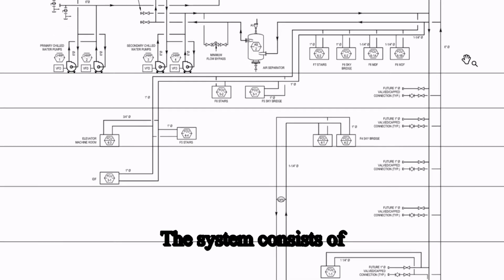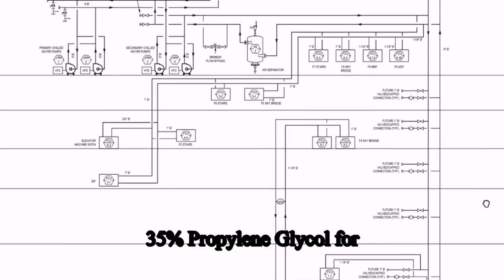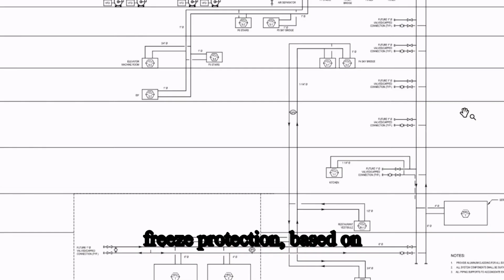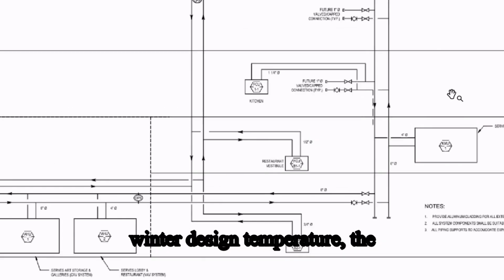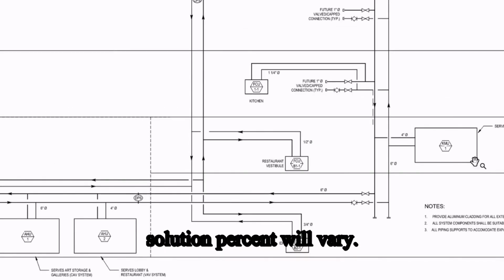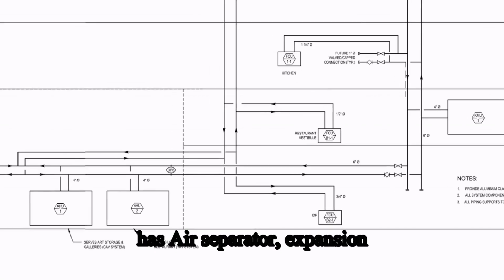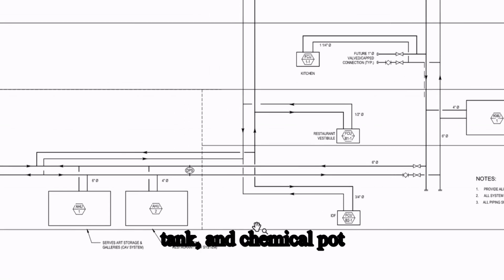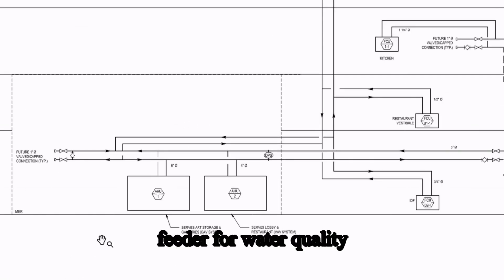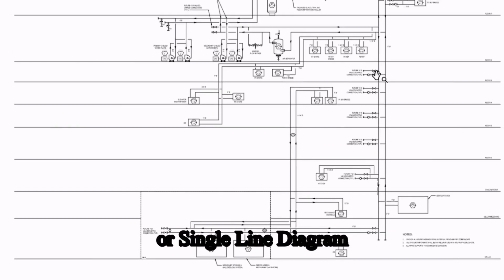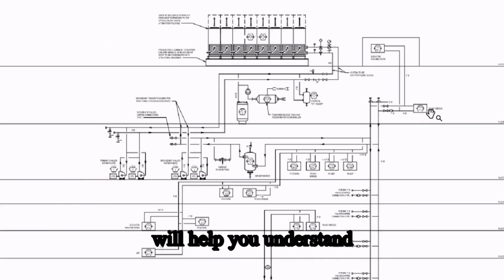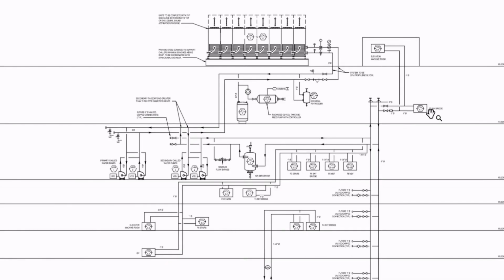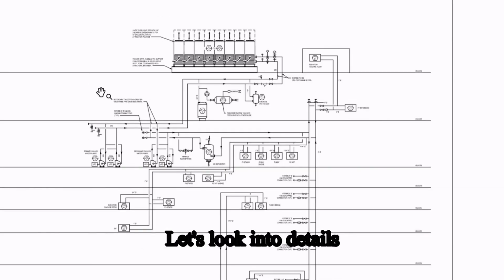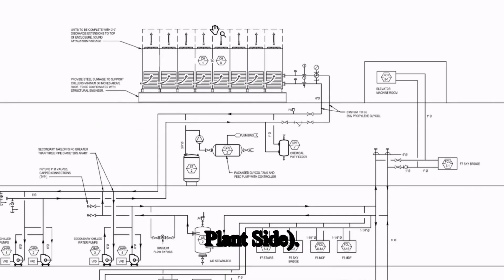The system consists of 35% propylene glycol for freeze protection. Based on winter design temperature, the solution percent will vary. The chilled water loop has an air separator, expansion tank, and chemical pot feeder for water quality and system stability. This chilled water riser or single line diagram will help you understand the system in detail and help you in your future project. Let's look into details of the primary loop, chiller plant side.